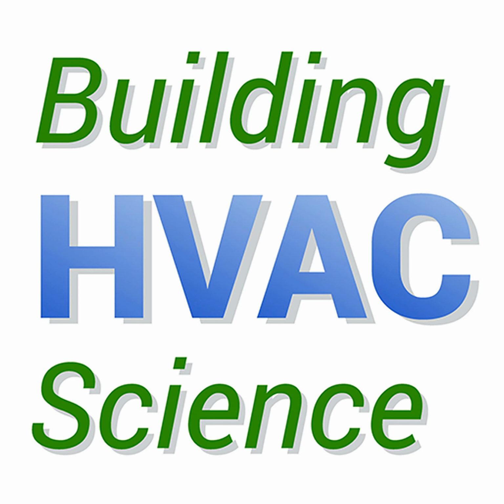In principle, yeah, there are two ways you could do that. It's not something we offer today because we haven't had a lot of customers ask for it. One way is you could have a water fill line going into the absorber. Say you have a data center and want to hold humidity at 60% plus or minus 5%, you could have a valve controlled by humidity. If you put water into the absorber and mix it with the desiccant so it dilutes, it will actually humidify, since it becomes more humid than your target.